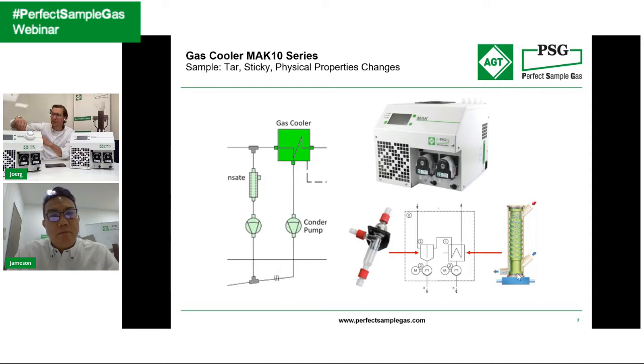Now, depending on the system configuration, to make this clear, here we're talking about emission monitoring, about the measuring itself. What we do now is crucial, because from the hot gas phase at 180 degrees C, you'll have a short pre-cooling so that the PTFE or PFA tubing you use to connect to the gas sample cooler or conditioning system won't be heated, in order to achieve this pre-cooling.